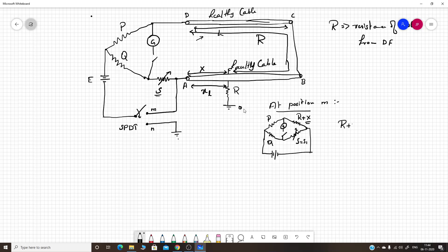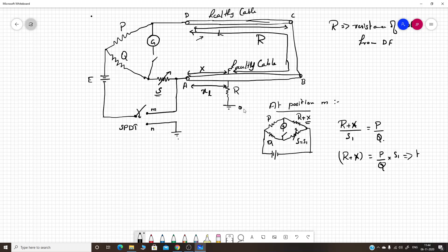At balance for position M, we get the equation: (R + X) / S1 = P / Q, or equivalently, R + X = (P/Q) · S1. From this we find the total loop resistance of both cables combined — this is the loop resistance.